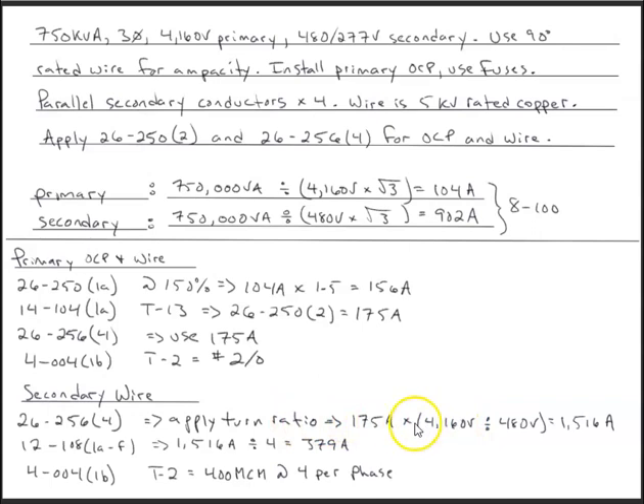So we have the 175 amps times the turn ratio, and again this is in line with how we've calculated in the past when we had test 1 and we did the turn ratio calculations. So 175 amps times the turn ratio, we're looking at 1516 amps on the secondary. So we're going to parallel the secondary, and what we're looking at here is 12108 subrule 1A through F deals with the specifics of installing parallel conductors.